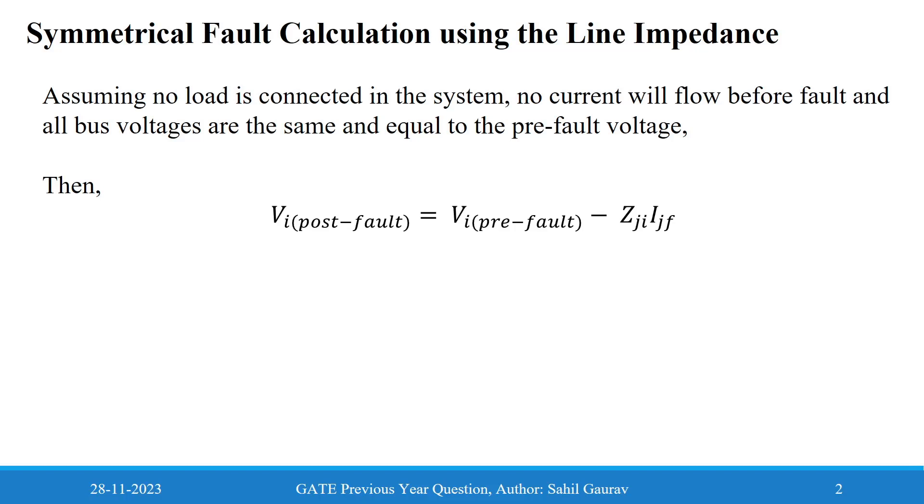We have to first assume some things so that we can apply this expression. Here we have assumed that no load is connected in the system, no current will flow before fault, and all the bus voltages are the same and equal to the pre-fault voltage. So we can find the post-fault voltage at bus I using this expression V_i(post-fault) = V_i(pre-fault) - Z_ij * I_fj, having the line impedance connected between the fault bus and the bus where we are finding the voltage.